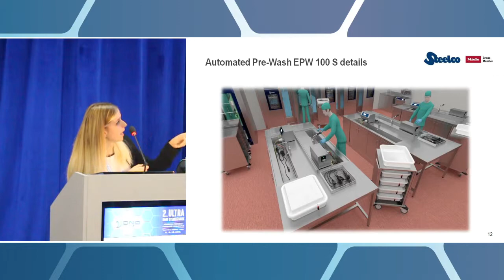the blue one there. But considering that when the scopes are arriving, they are arriving into transport systems with closed cassettes, then we also need to reprocess these cassettes besides the endoscopes, to have clean ones. So we have also introduced here in this very special endoscopy department also some trolley washers to wash the cassettes and the trolleys themselves. 2 doors, even here, pass through. You load them from one side and you unload them from the other.